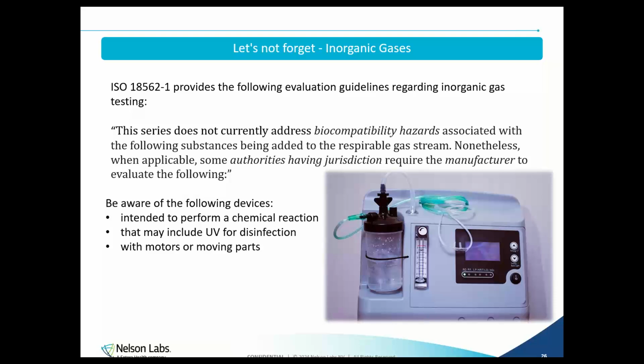Nonetheless, when applicable, some authorities having jurisdiction require the manufacturer to evaluate the following: ozone, NO2, CO2, and CO. So, as a medical device manufacturer or a CRO, we must always be on the lookout for various devices that are intended to perform a chemical reaction, that have UV for disinfection, or any devices with motors or moving parts. This testing may be easy to overlook, and we just have to catch it ahead of time.